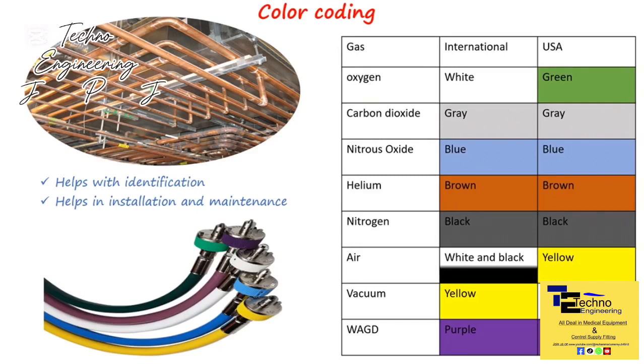In the international standard, oxygen pipes are designated as white, while in the US standard, they are green. Carbon dioxide is represented as gray, nitrous oxide as blue, helium as brown, and nitrogen as black in both coding systems. Medical air is indicated by white and black internationally and by yellow in accordance with the US standard. The suction pipes or vacuum is coded yellow and white in international and US standard respectively. Waste anesthesia gas disposal is coded purple by both systems.